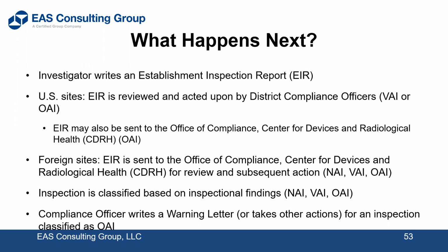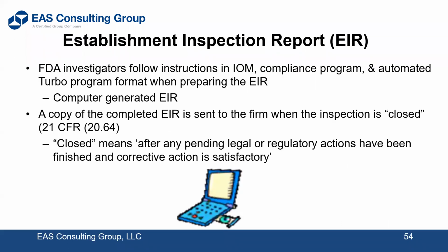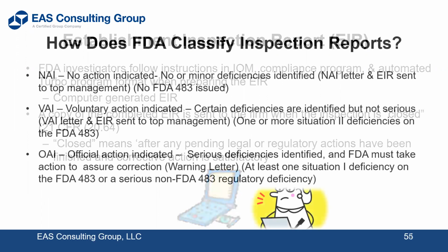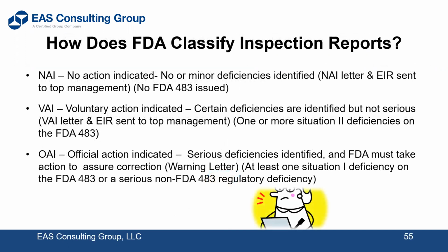So with medical devices, everything that's in situation one, as I explained earlier, is OAI. Everything else is VAI or NAI. So FDA writes it up, and if it's VAI or NAI, you get a copy of the report after it's closed. This is only for medical devices. So again, NAI is no action indicated. That means minor things that they don't put on the 483, or no problems at all. VAI is the situation 2 deficiencies, one or more of those.